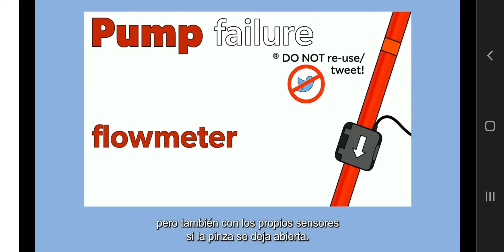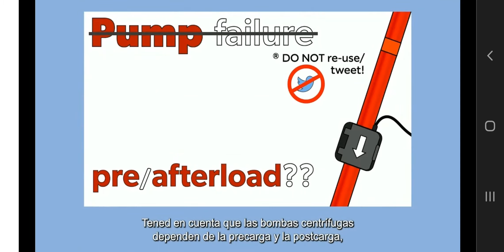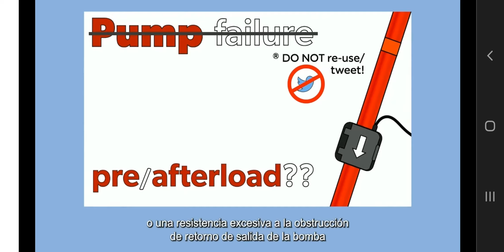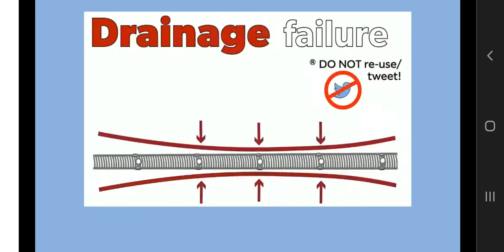This could happen during the run, particularly with old flow meters, but also with actual sensors if the clamp is left open. But sometimes you have an impaired blood flow or you do not have a blood flow at all, but the pump is not failing. Consider that centrifugal pumps are preload and afterload dependent, so a significant lack of preload, drainage failure, or an excessive resistance to pump output, return obstruction, will impair the flow even with a potentially perfectly working pump.